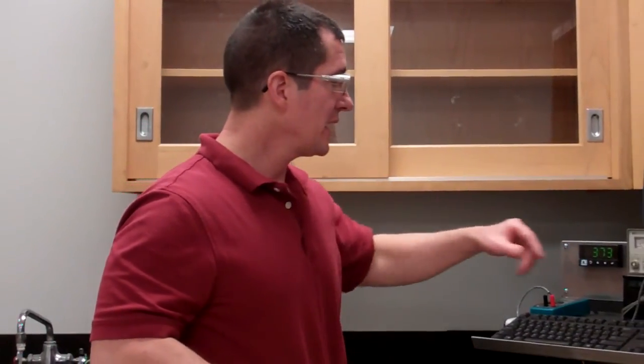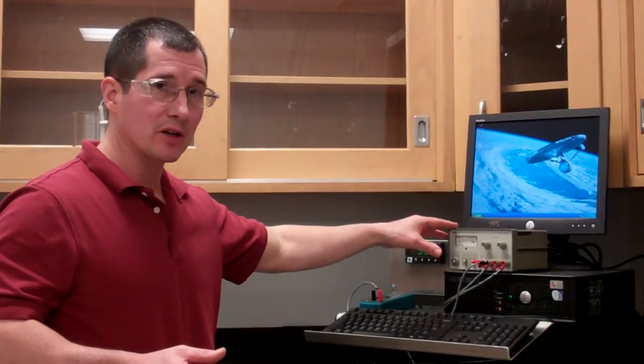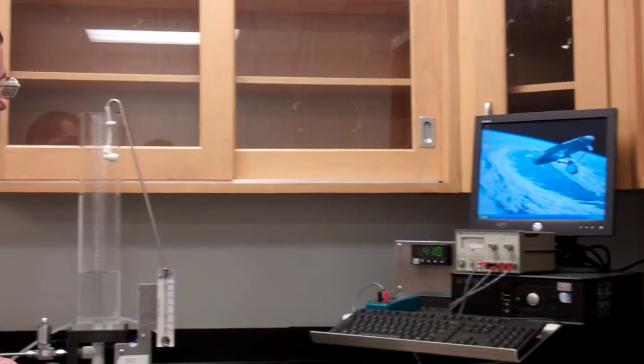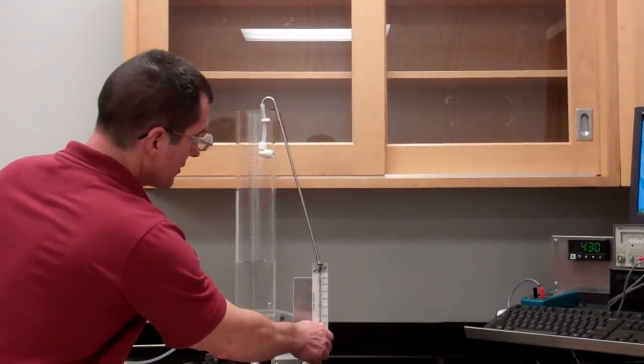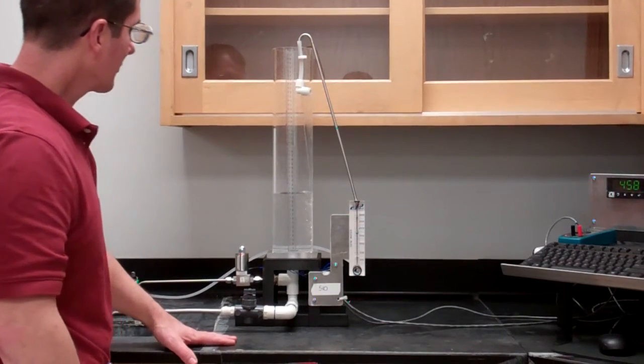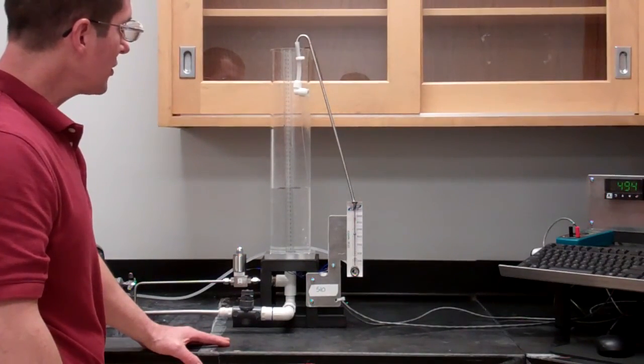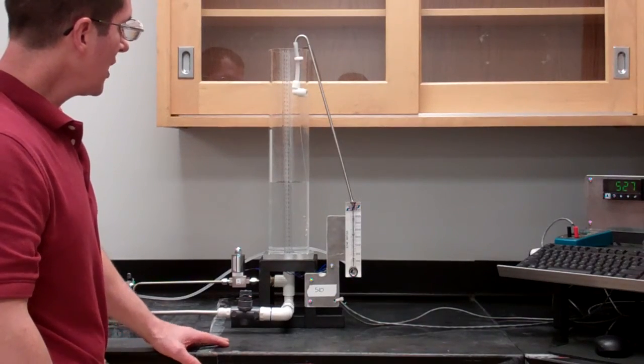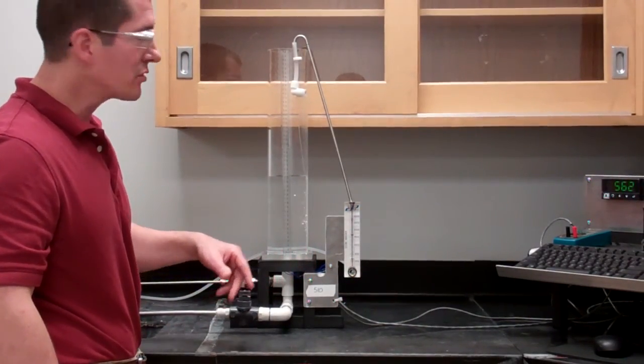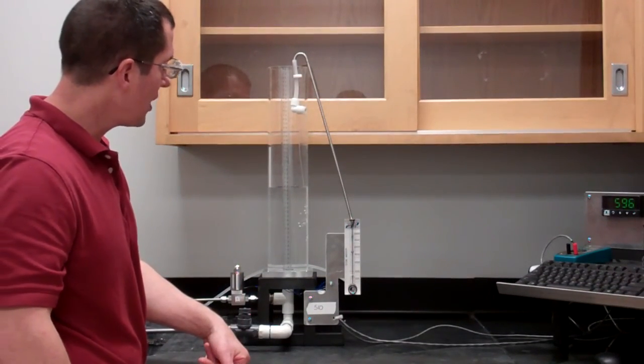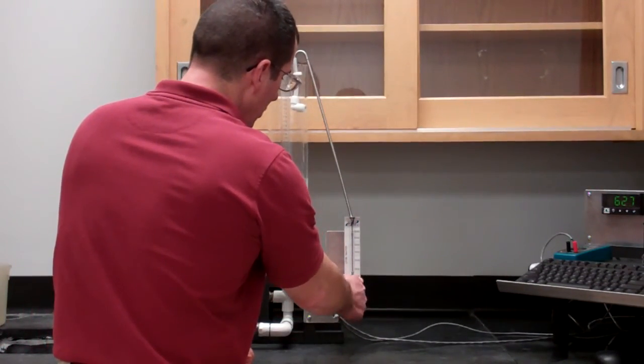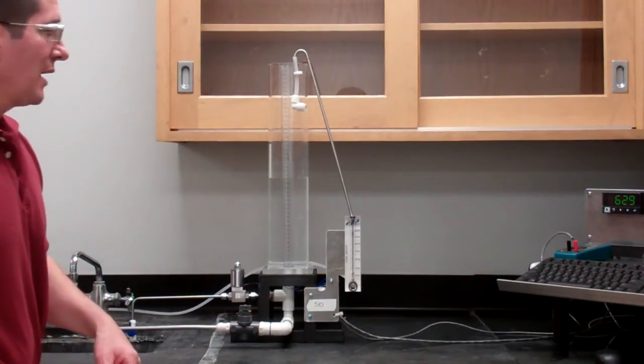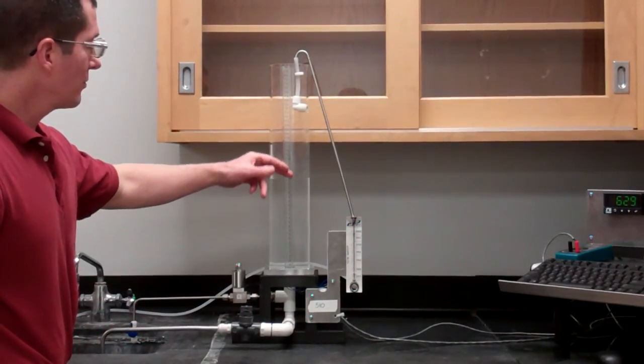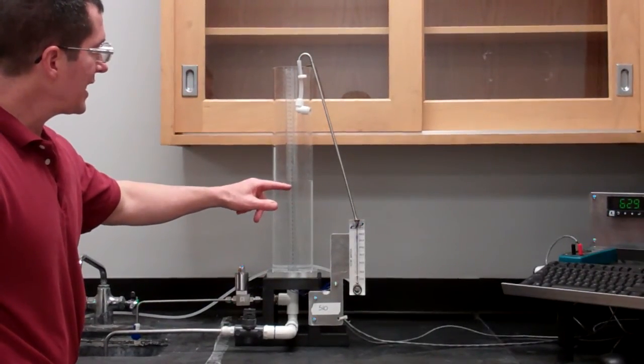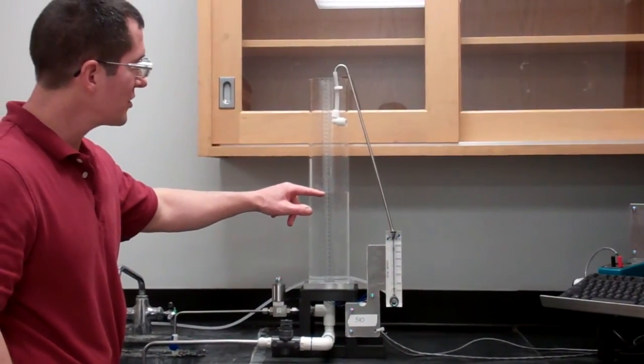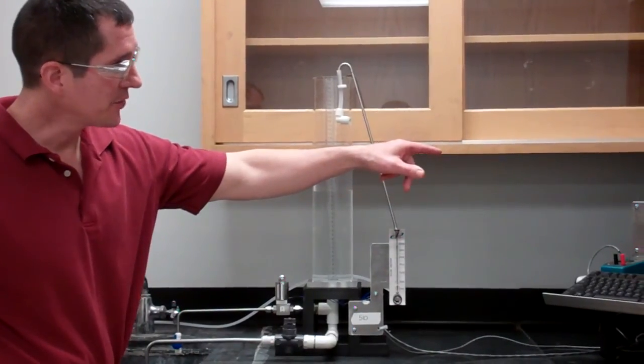What we're going to do for the first experiment is you are going to be the controller, and we're going to operate this system manually. So I'm just going to put some water in the tank. One of the things you're going to need to do is characterize the transducer output as a function of the water level height in the tank. If I put some water in the tank, we'll let it settle there. The ruler on the side of the tank is in centimeters on this side, so you'll use centimeters. You measure the centimeter height of water in the tank and also record the counts.